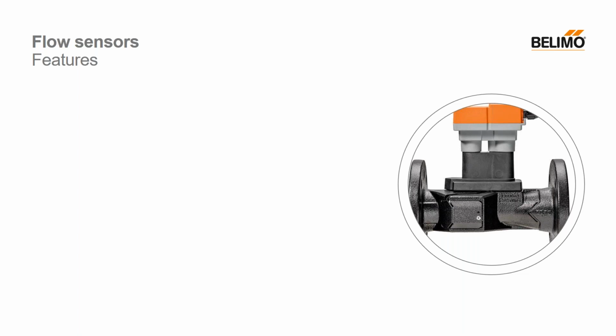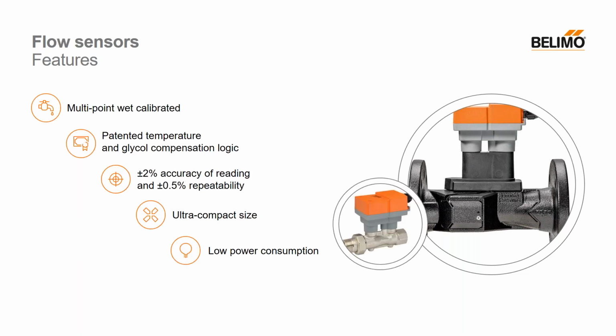And these valves use flow metering devices to maintain pressure independent control across the range of the output from the controller. When we initially introduced the EPIV and the energy valve, we used something called a magnetic flow meter. And over time, Belimo developed their own ultrasonic flow meter technology. So instead of employing technology that someone else manufactured for us, we developed ultrasonic flow metering technology that is used in our electronic pressure independent valves and our energy valves, but it is also available as a standalone analog output flow meter. So these are going to be calibrated, multi-point wet calibrated flow meters.